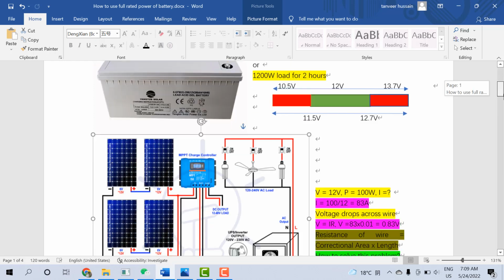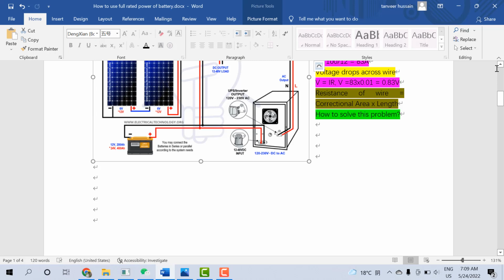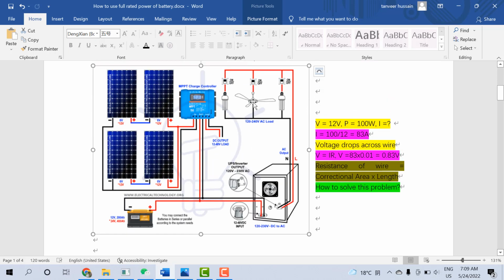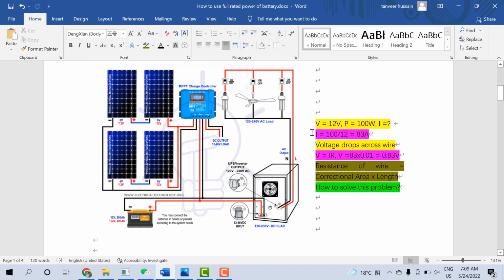Now say you run your load at 70% and turn off all other inputs. If there's a voltage drop, let me give you an example calculation. If your load is 1000 watts and your battery is 12 volts, the current on this wire would be 1000 divided by 12, that is 83 amps.